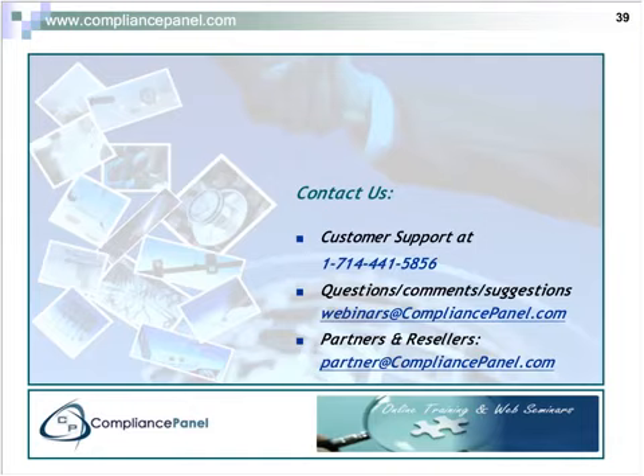So if you go through 21 CFR Part 800 on the web page, you can find a category that your product falls into. In reading through all of the different products listed there, if you can say, hey, this is my product, and it gives you the requirements for it, then I would say you need to register with the FDA. You need to register that device before you sell it, and you need to follow the 21 CFR 820 requirements. Okay. Thank you. You're welcome.